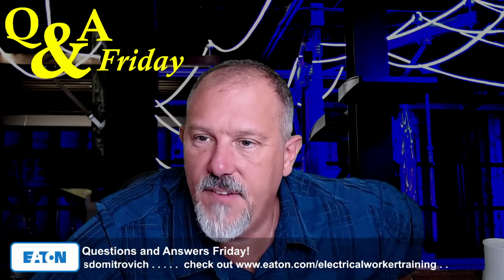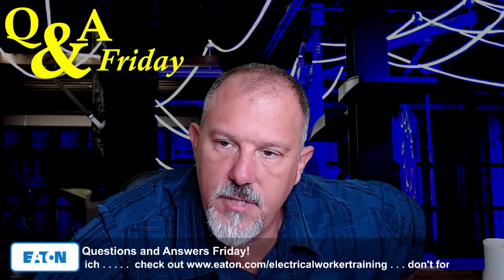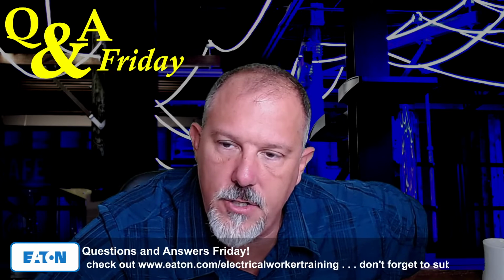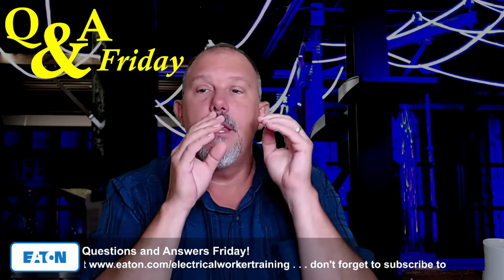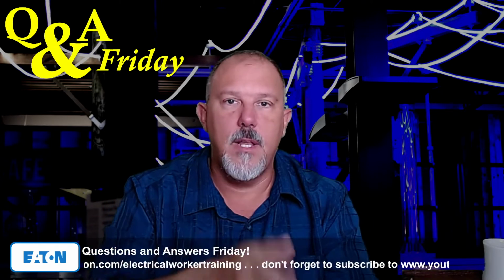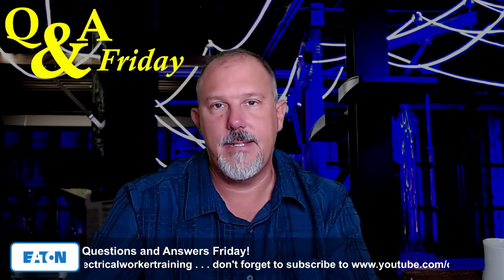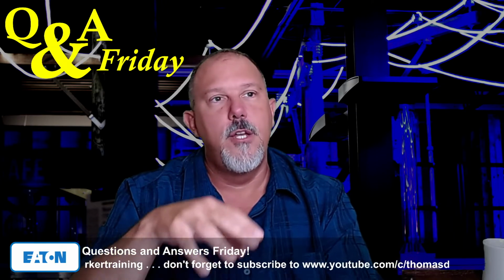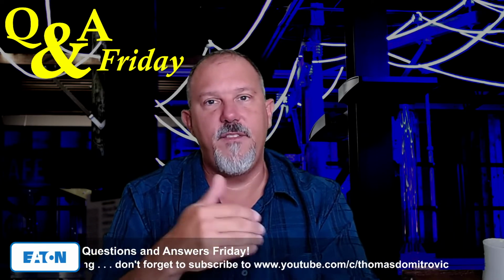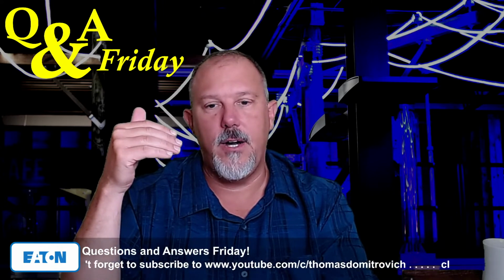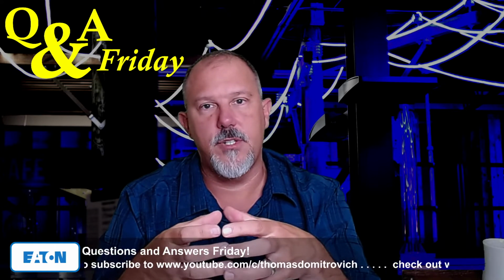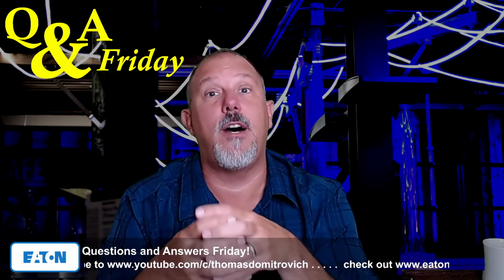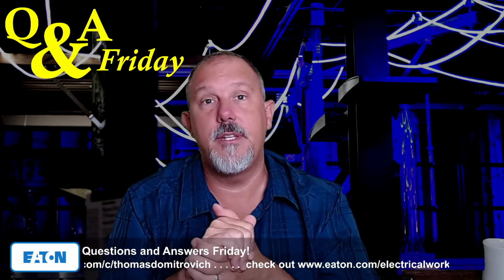Is the 125% requirement to prevent damage to OCPD or equipment or to prevent nuisance tripping? The 125% is to align with how the product is tested in an assembly. So when we add the 125% in on a conductor, we increase the conductor size because I need that copper to help pull heat off of the device.